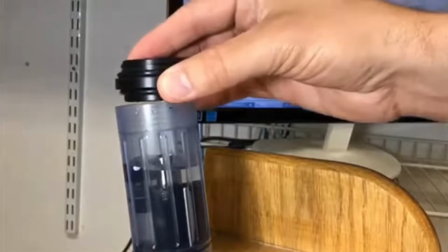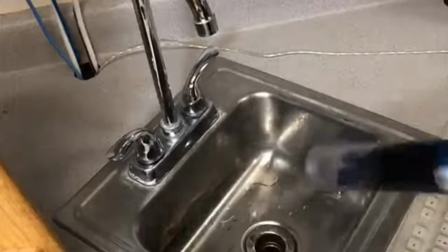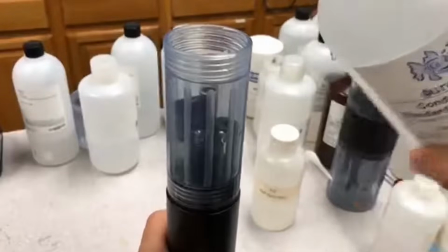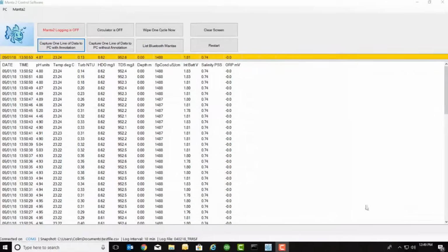First, do your rinsing process. We recommend 2 rinses first with water, and then 3 rinses with the solution that you will use to calibrate with. Once this is done, fill the cup until the solution covers the sensor.